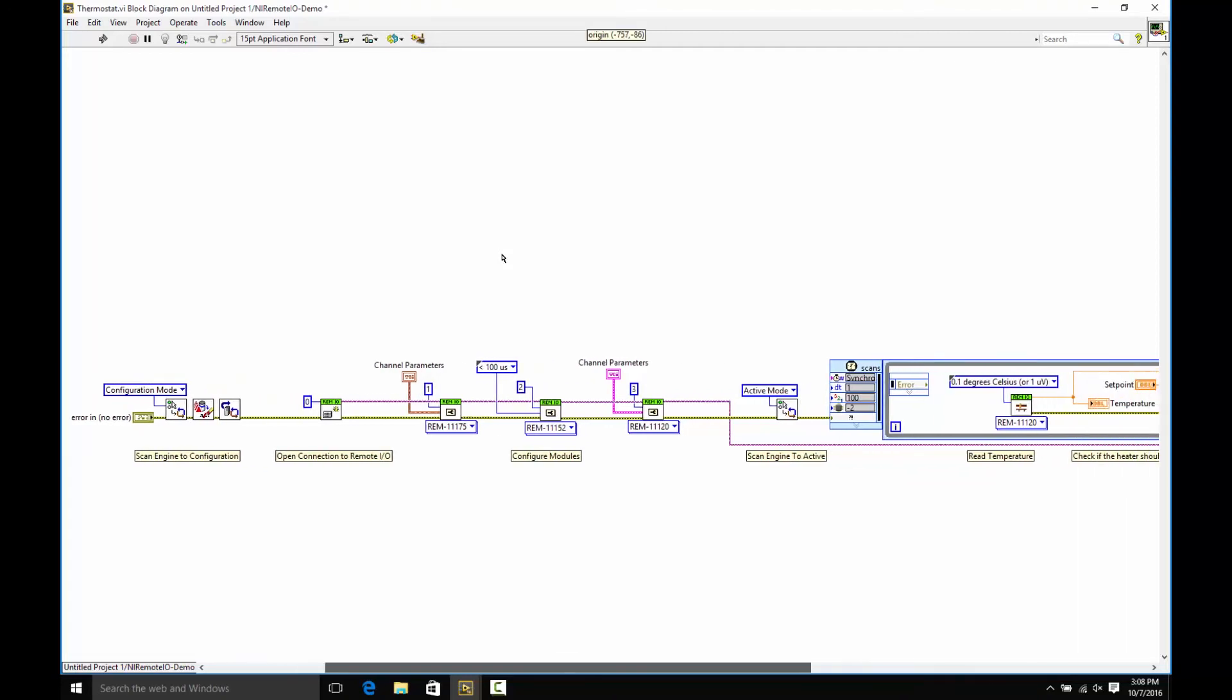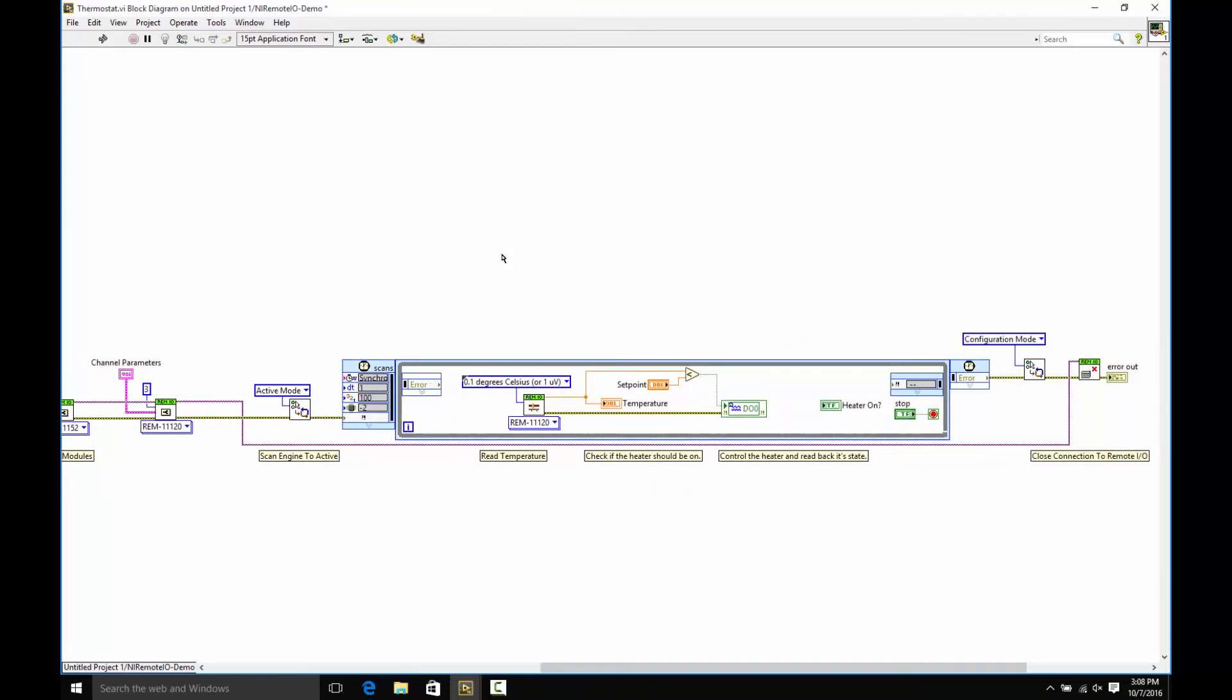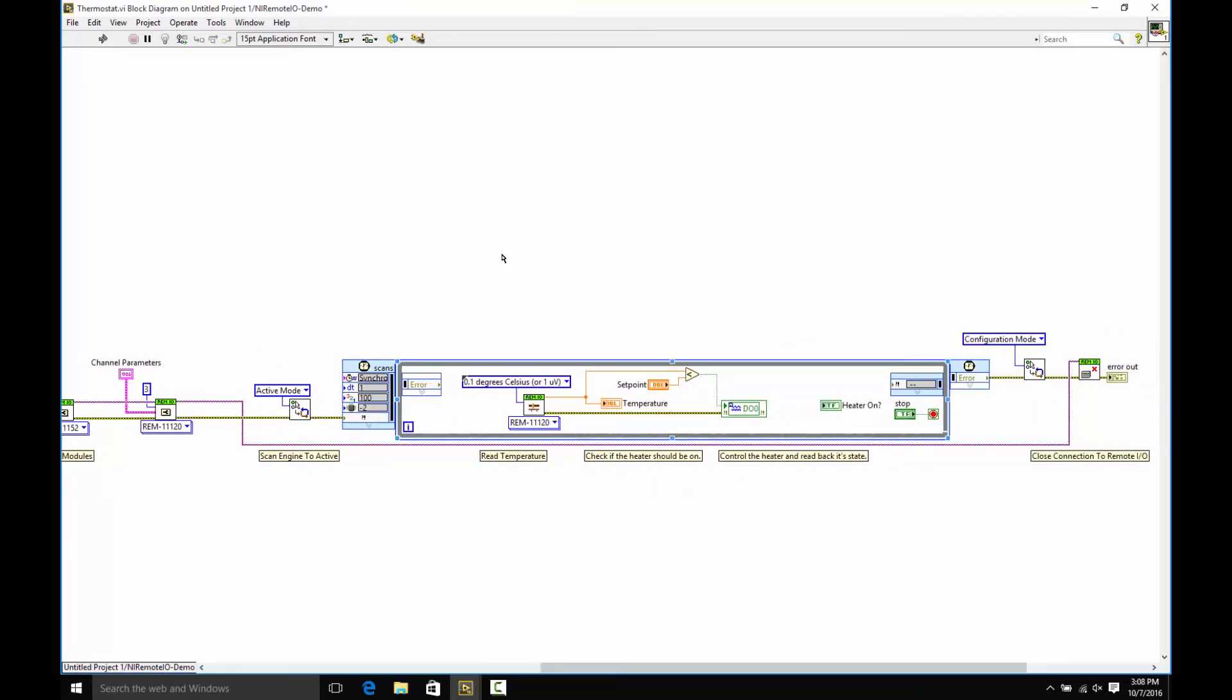Okay, once you've configured the modules, you set your scan engine to run, and then you read your I.O. inside of a timed loop that is synchronized to the scan engine. Inside this loop, we're going to drop our I.O. variables from the project.